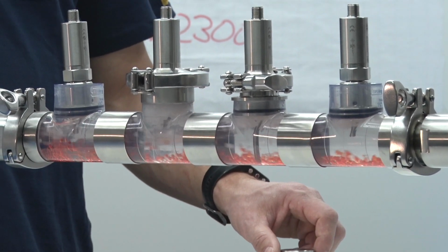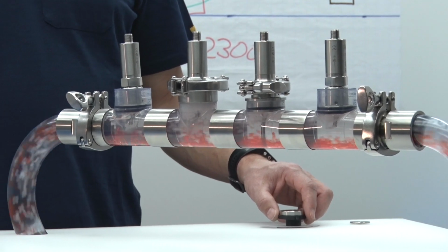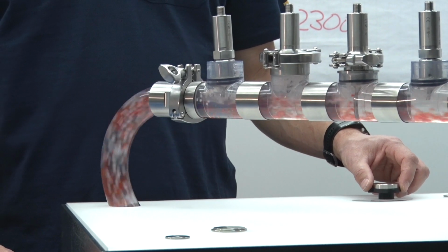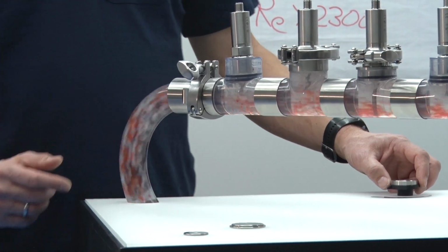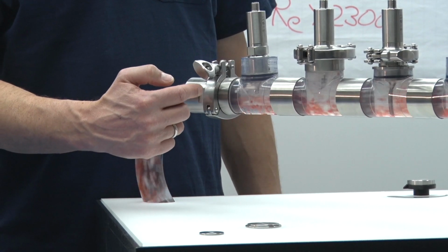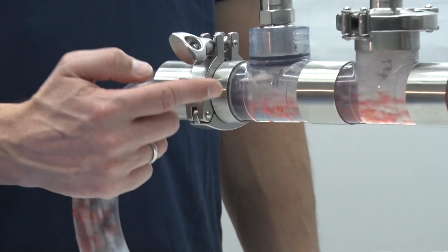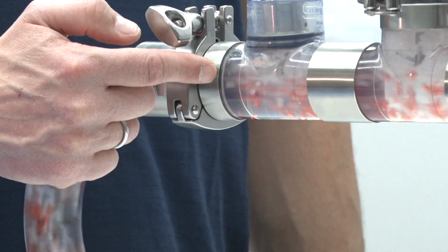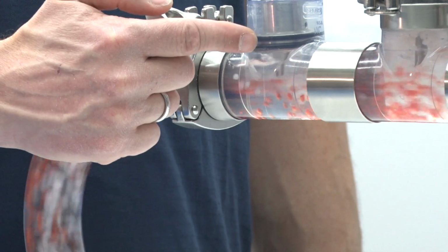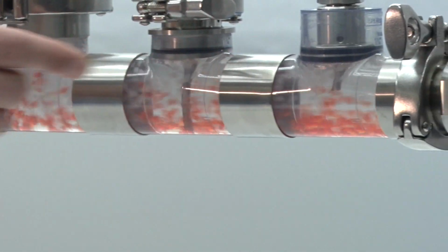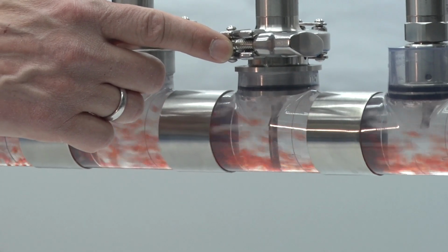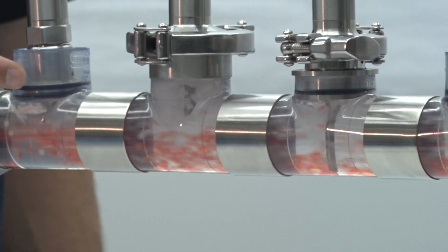With speed increased up to the maximum, you can see flow dynamics changing from laminar to turbulent. This is the maximum speed of the model here. Then you see that the spheres are no longer in the same flow but start swirling in the pipe. With that we have turbulent flow. Now the sensor installation position is no longer relevant. The sensor will return the same flow information in each position from 1 to 4. Nevertheless, some residual effect may remain if the sensor tip is too close to the pipe wall.